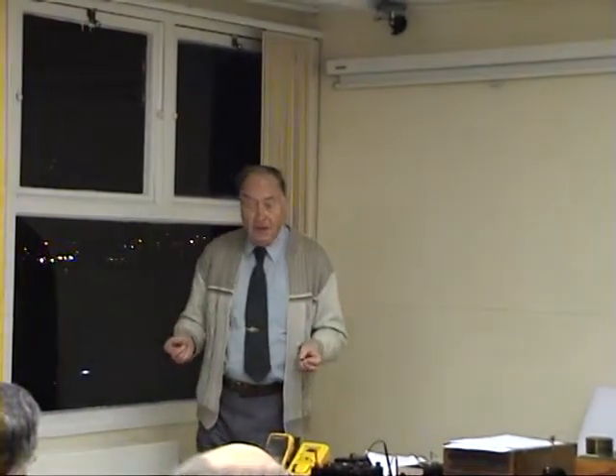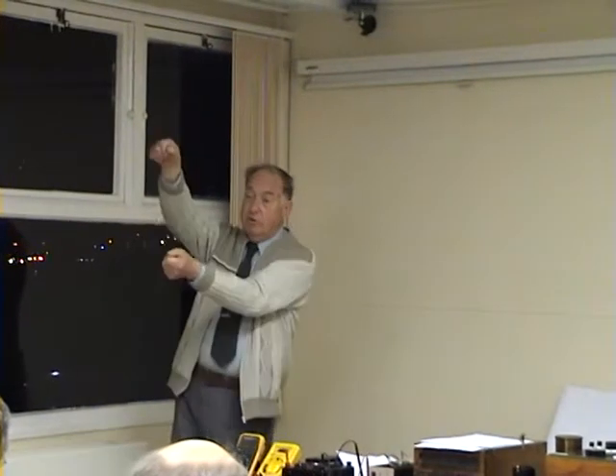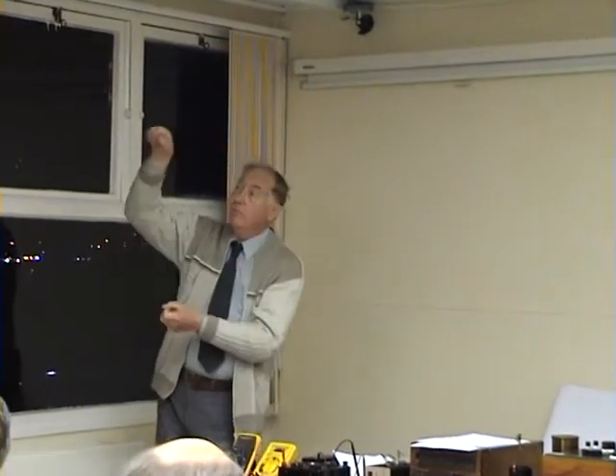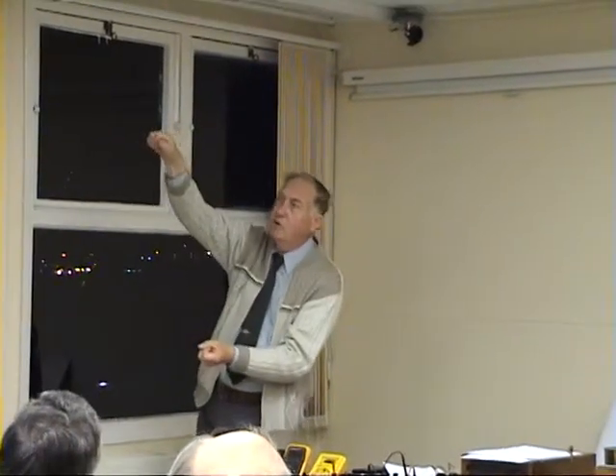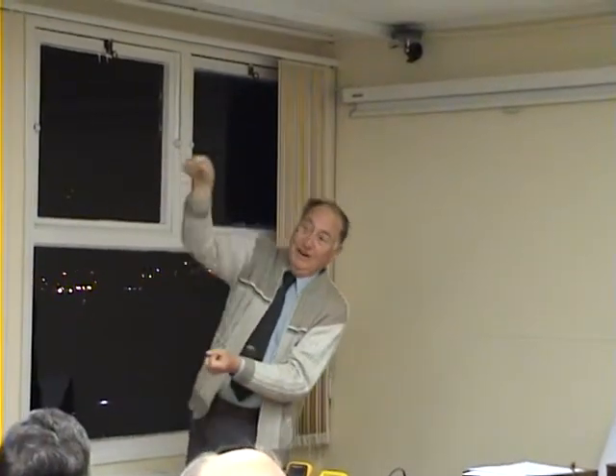One of our test engineers went out on site, and UPSs have a DC bus bar in it. It runs at 350 volts and is virtually unlimited amps for a second or two if anything goes wrong. And he was taking a measurement voltage reading across this. I'm doing this because this is how the system was. The test point is up there, the earth is down there, and it goes across the bus bar on the voltage range. Yep, 350 volts.